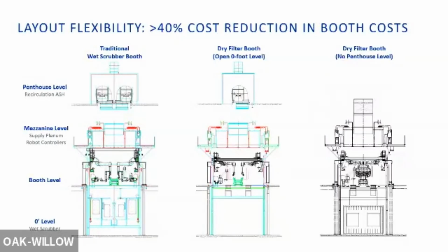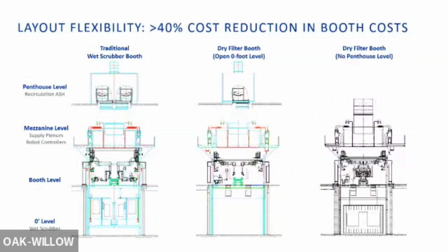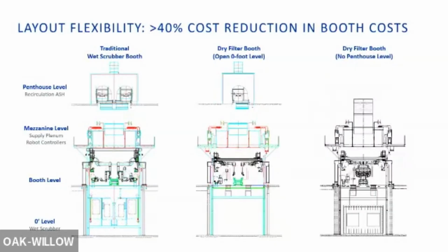And on the far left is our traditional spray booth that requires 4 levels of booth-related equipment. And I'll just take a moment and step through each layer from the top down, which is the direction of our airflow, to show what happens at each layer. So up in our penthouse layer, we have our recirculation air supply house. It's really nothing but fans in a big metal box. Inside that metal box is some filter banks and a chilled water heat exchanger or a cooling coil, and then also a hot water heat exchanger or a hot water or reheat coil.